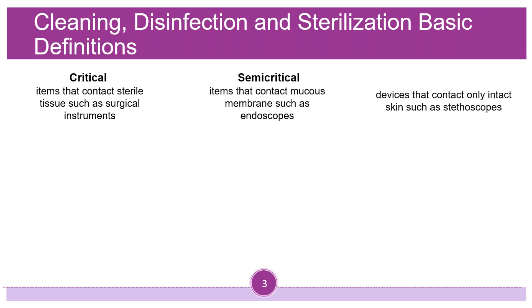Okay. So cleaning, disinfection, and sterilization, basic definitions. We have 3 primary categories that medical devices fall under, depending on what type of tissue that item is going to come into contact with. So items that contact sterile tissue, such as surgical instruments, would fall under what category? Critical. Thank you. Next one, items that contact mucous membranes, such as endoscopes. Semicritical. Great. And then the very last one is devices that contact only intact skin, such as stethoscopes. Non-critical. Perfect.